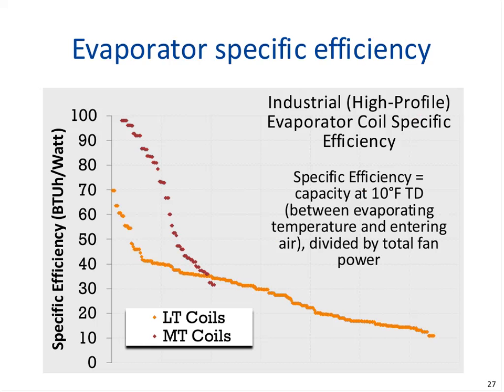And then here's a thought about that evaporator itself. And we know not all evaporators are created equal. Evaporators can be denoted as their specific efficiency in terms of BTUs of heat that they would absorb per fan watt. And notice here what we'll consider high efficiency evaporators absorbing 50 to 70 BTUs per fan watt. And here's our least efficient evaporators, only absorbing maybe 15 to 20 BTUs.